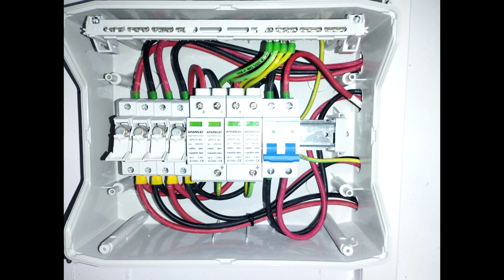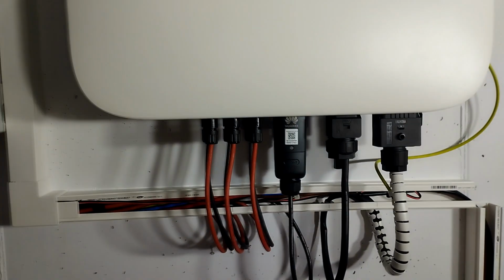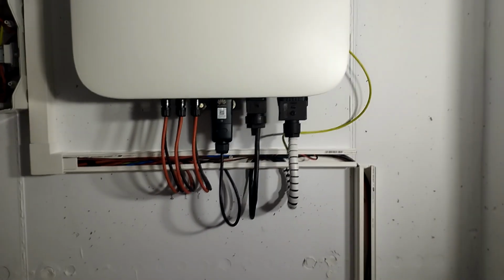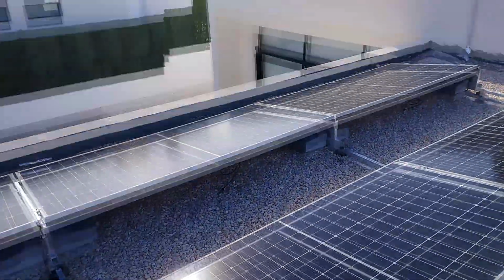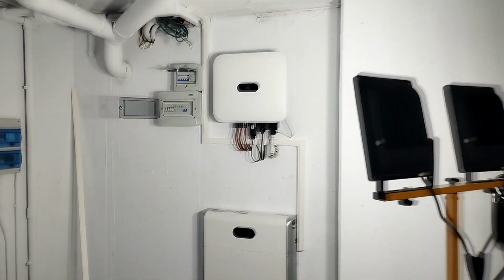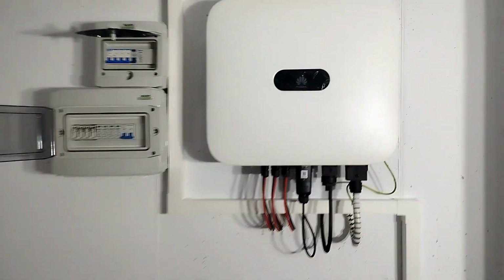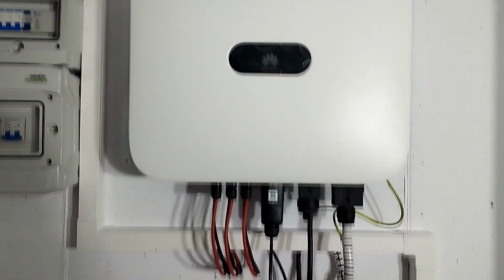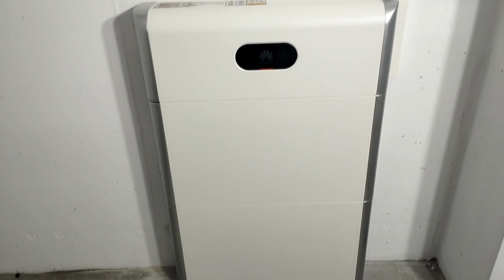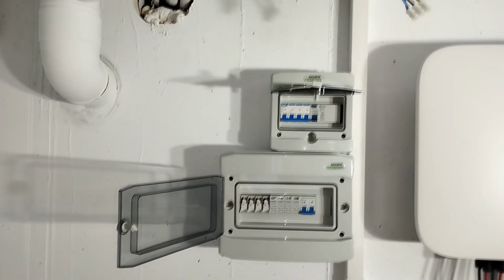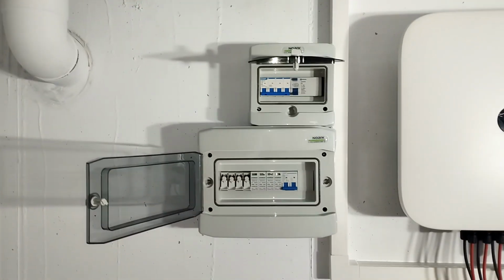Please also notice that the solar panels are divided into two independent strings, each connected to a separate MPPT input on the inverter. It is absolutely unacceptable to combine all panels into a single string simply to save on cables or labor. From all this, you can see our main competitive advantage. And no, it is not a low price. Our advantage is the high quality of the materials we use and the high quality of our workmanship. As a result, we hand over a solar power system that is ready for any inspection, even the strictest one.